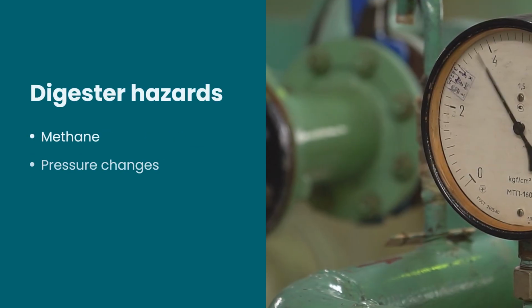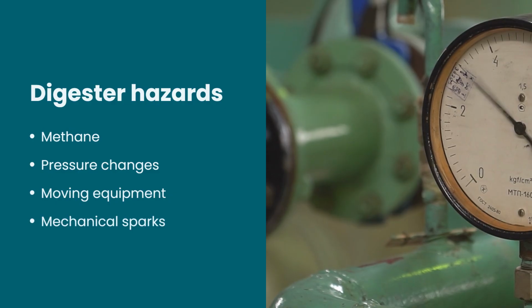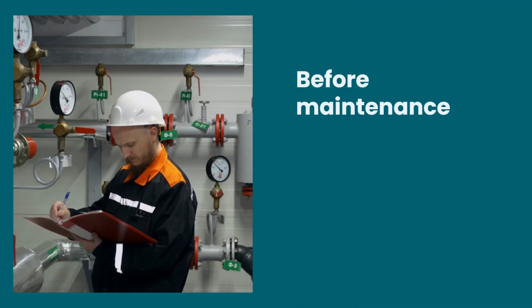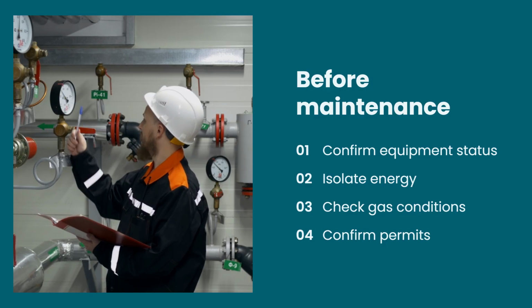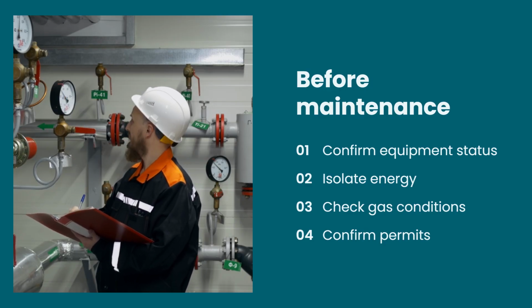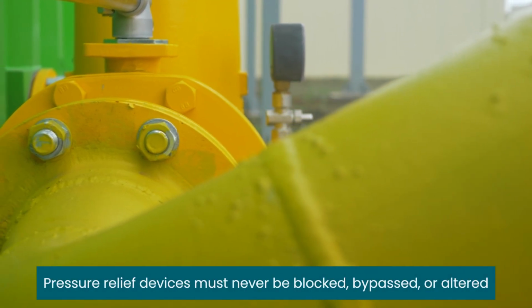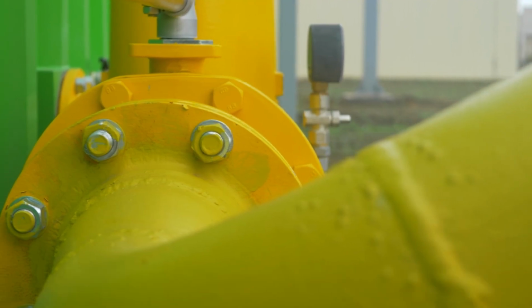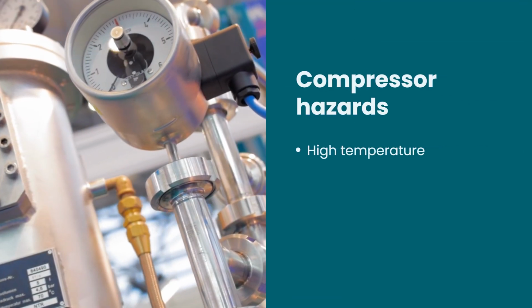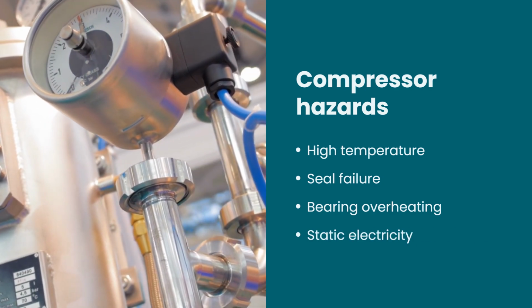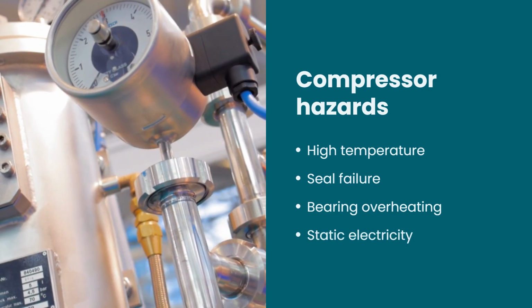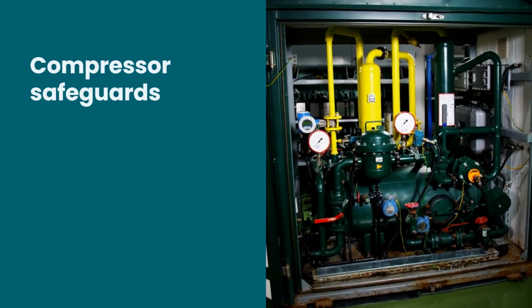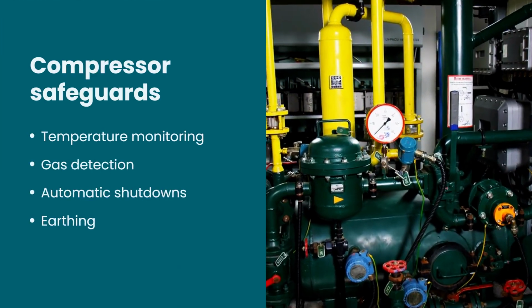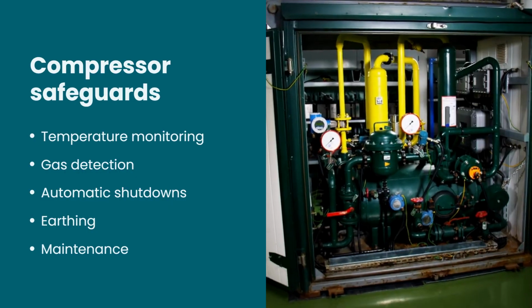Digesters combine methane, pressure changes, relief devices, moving equipment, heat, and possible mechanical sparks. Before maintenance, confirm equipment status, energy isolation, gas conditions, and permit requirements. Pressure relief devices must never be blocked, bypassed, or altered without formal authorization. Blowers and compressors face high temperature, seal failure, bearing overheating, pressure changes, and static electricity. Important safeguards include temperature monitoring, gas detection, automatic shutdowns, earthing, and preventative maintenance.